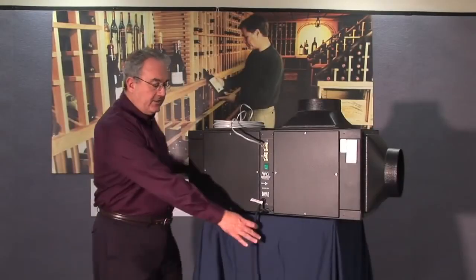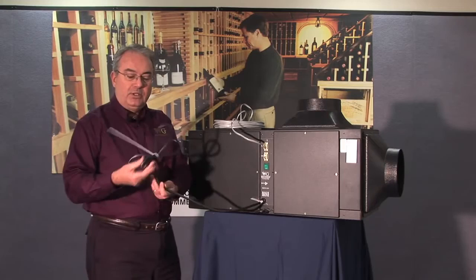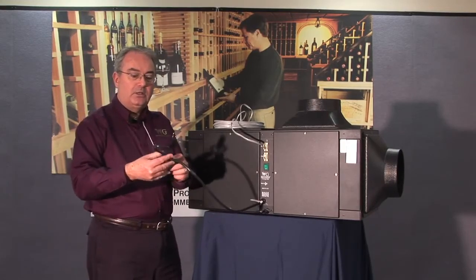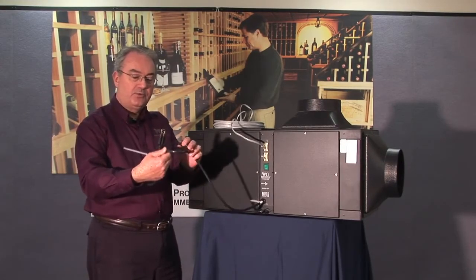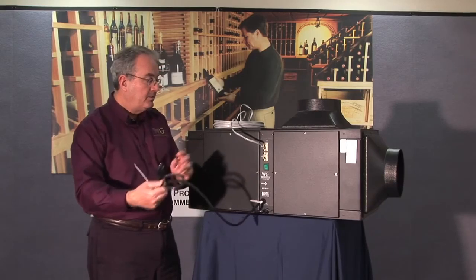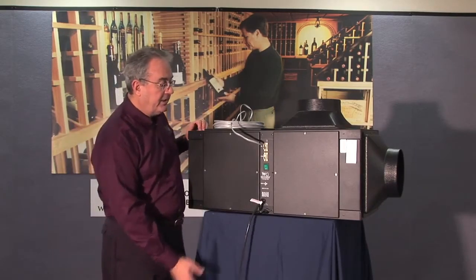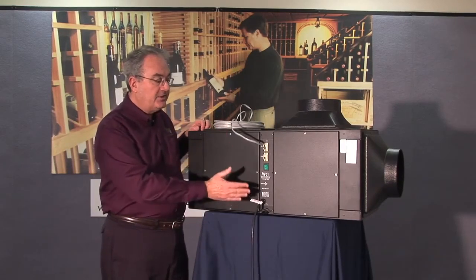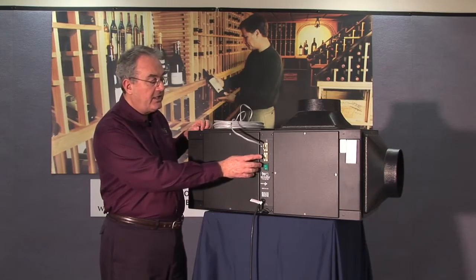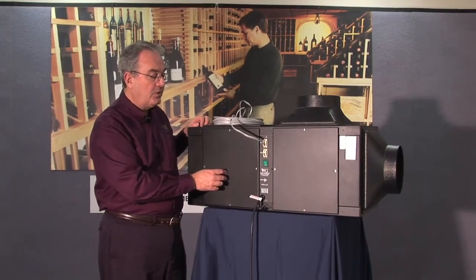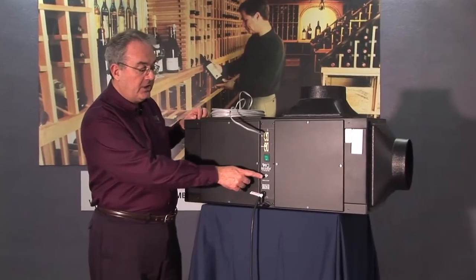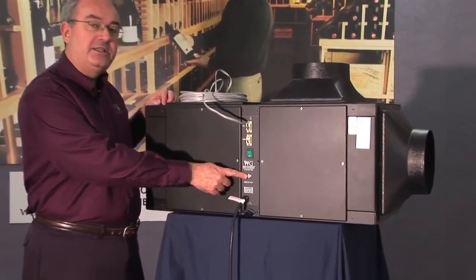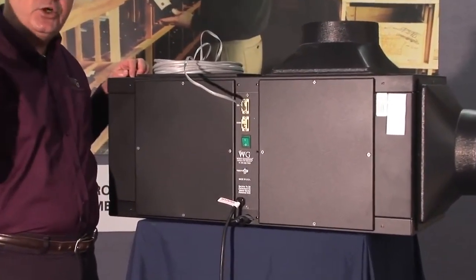A few of the other standard features. This unit really is plug and play. You can plug it into the wall using this cord. Obviously on our export units there's a different plug, but you can plug it right in. Notice that really all of the things you need to work on once the unit is installed are on one side here. You have 2 communications ports, you have an on and off switch, and you have a connection in case the humidifier is installed remotely.